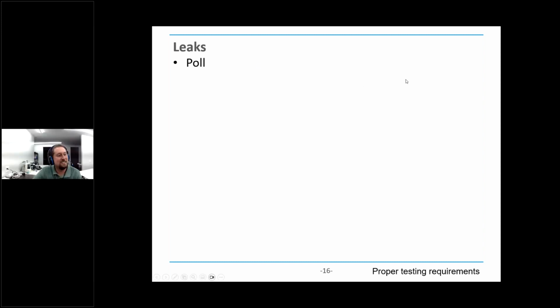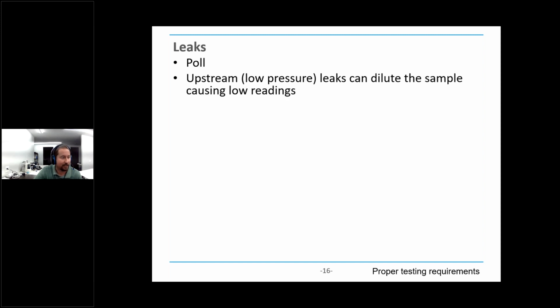That's awesome. So leaks are actually a real problem with gas monitors. That's the one downside of these side stream gas monitors. If you have a leak, it can dilute the sample. It will actually mix room air in, because it's a vacuum, it's sucking that in. It can mix room air in with the sample and you get really low readings compared to what they should be. And so leaks are a problem.